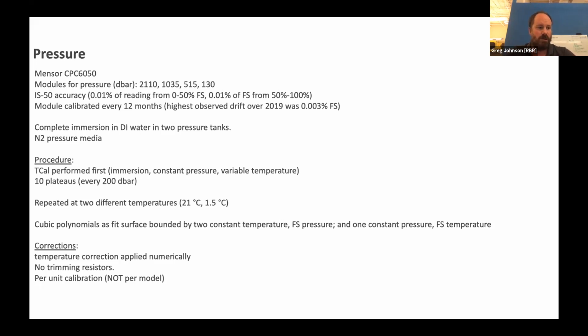There's a number of reasons we don't do that. One is that a linear correction is not sufficient. And the second is that it's a very crude technique, and the trimming resistors introduce more errors themselves because they typically have some degree of temperature stability problems themselves, unless you get extremely expensive ones. And so that temperature correction is applied per unit. So each gauge that we ship, the logger knows how to correct the temperature effects on each of them.